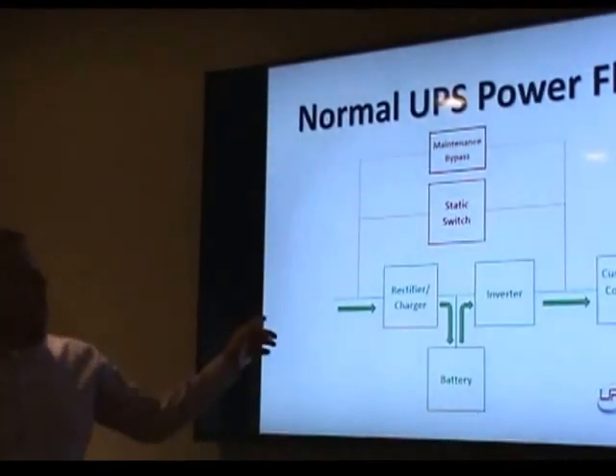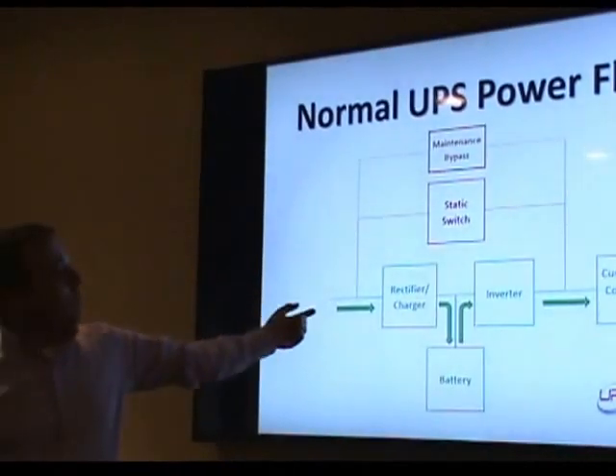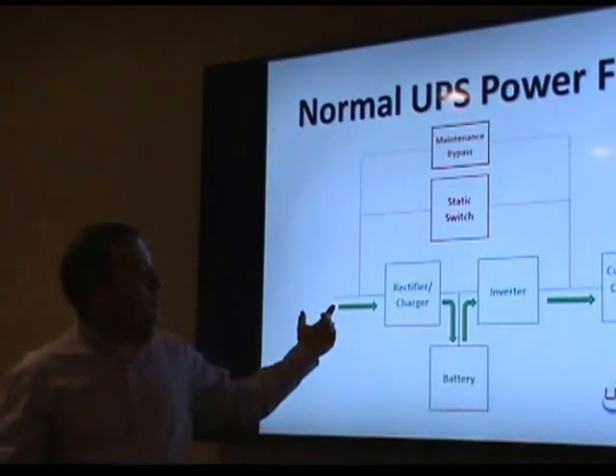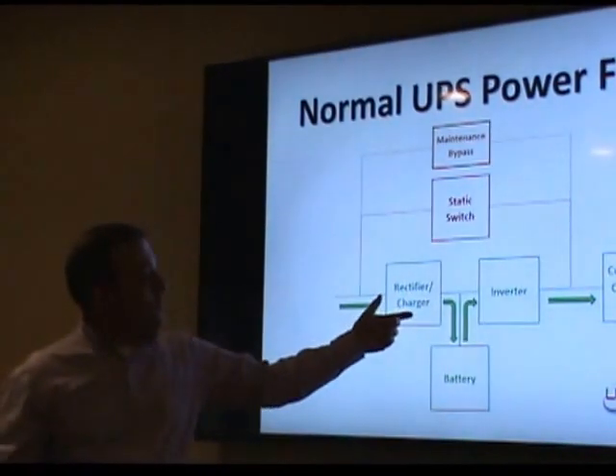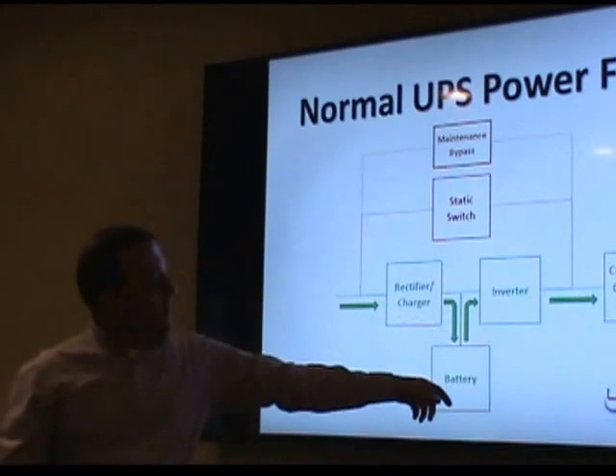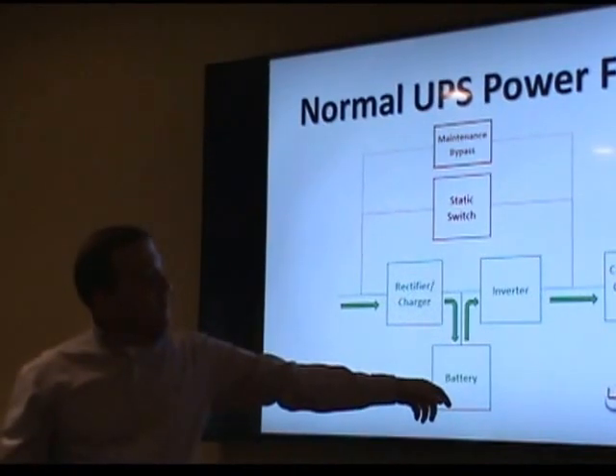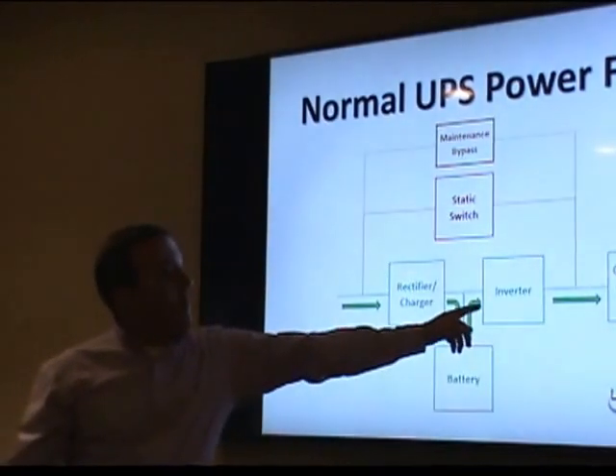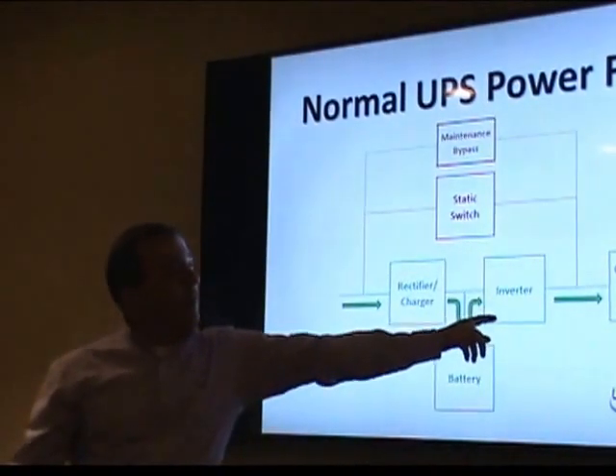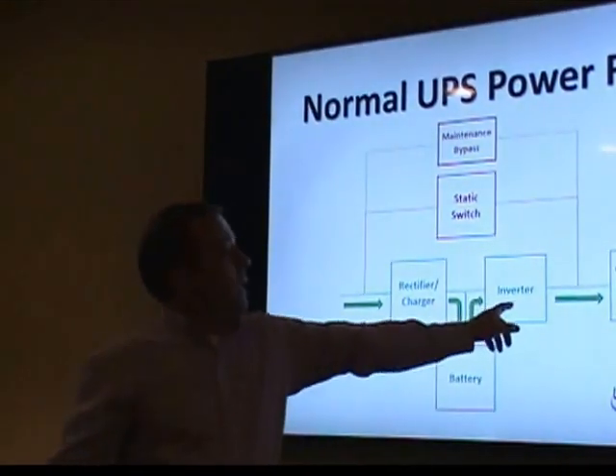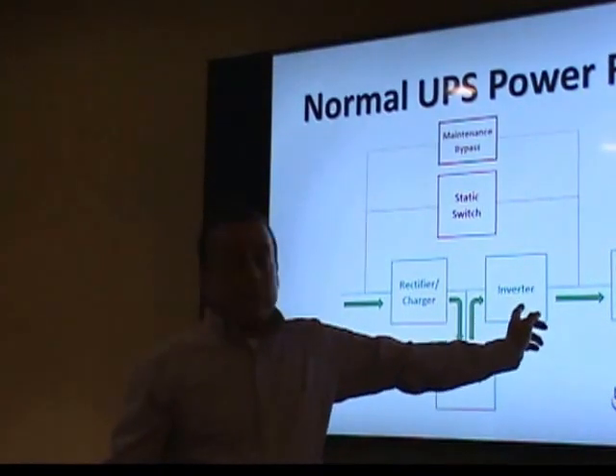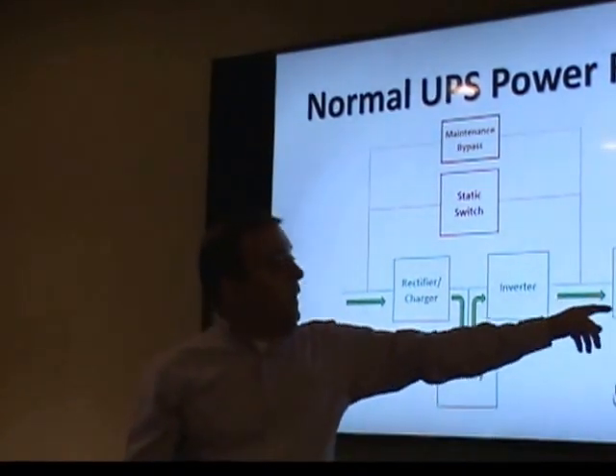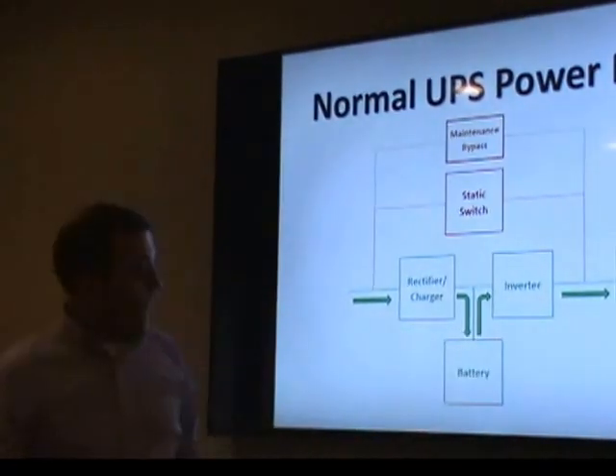So like I was saying, this is the power flow for a UPS system. Power comes in from the wall through the charger, continues to charge the batteries, from the batteries to the inverter. The inverter makes it from DC back to AC and then out to the computer load.